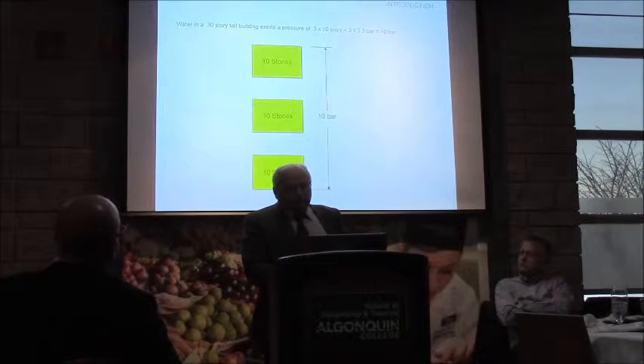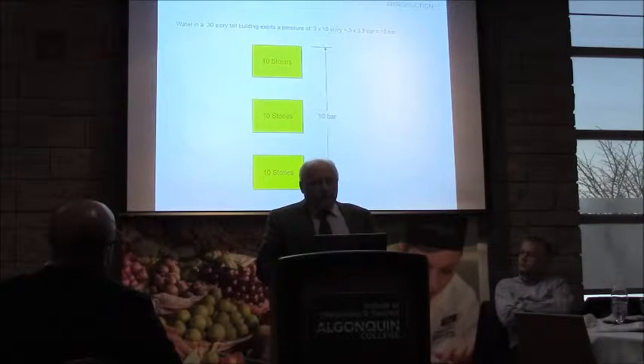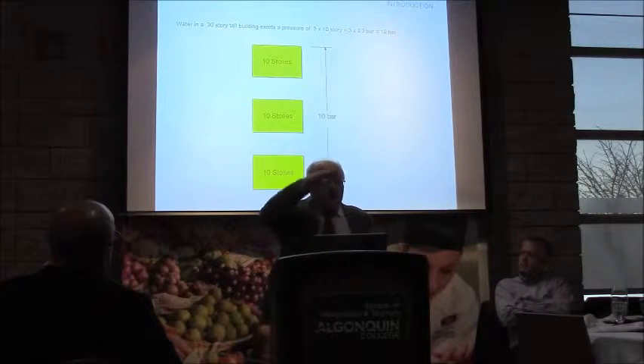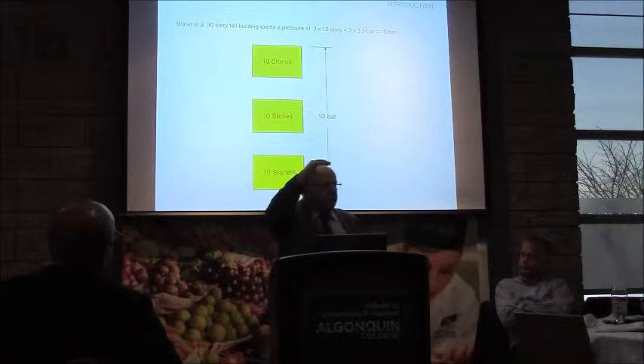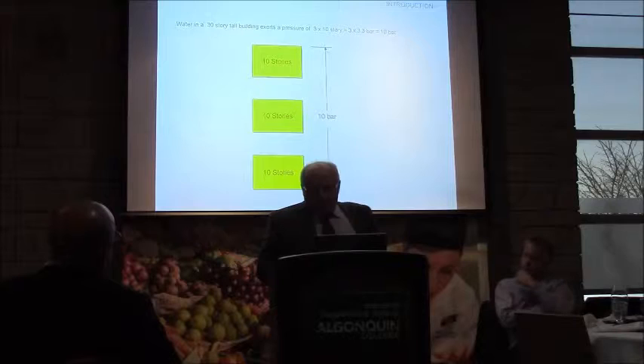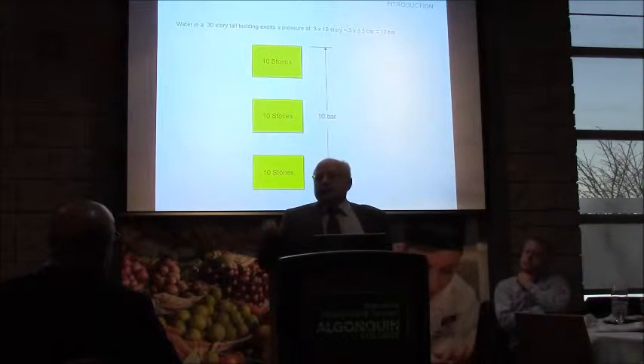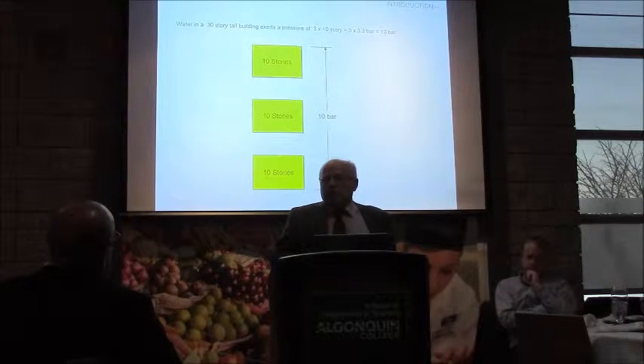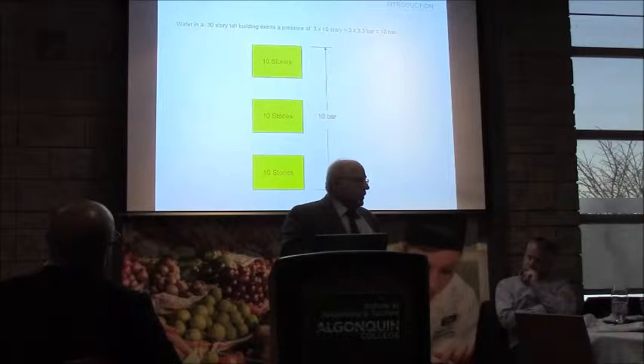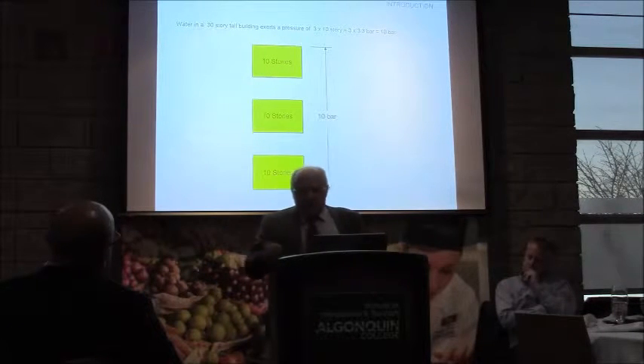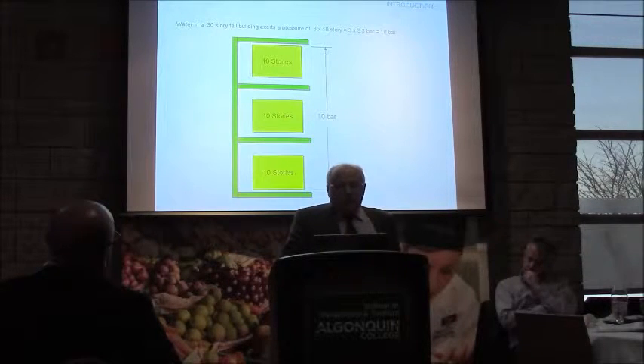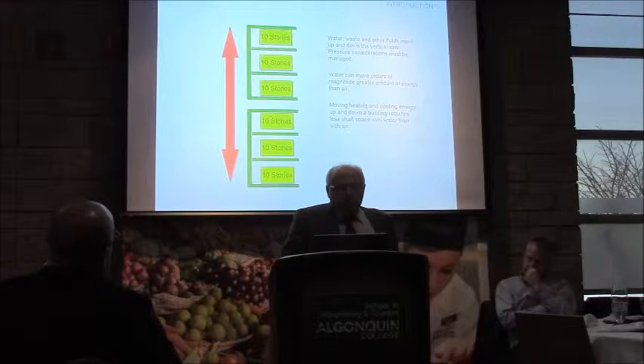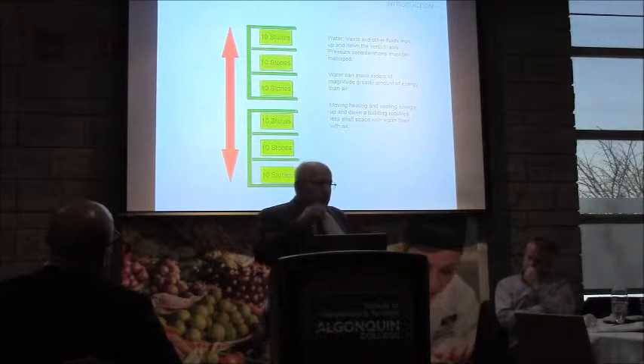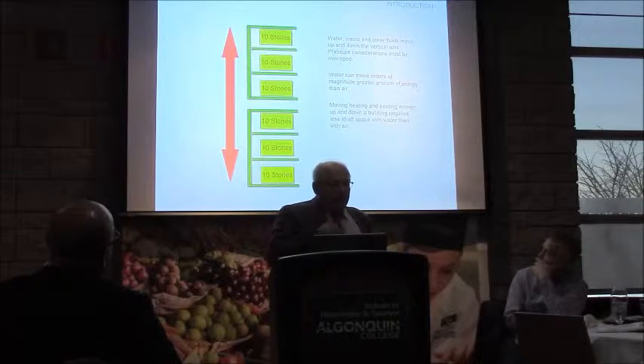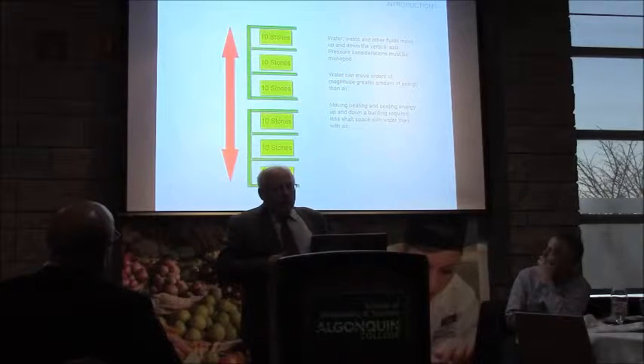Clearly then, the interface pressure with occupants becomes an issue. Material pressure limits and deciding where these breaks occur, is it 10 stories, 12, 9, 8, 15, it can depend on what we're talking about, whether they're systems that have to be closely regulated to a smaller pressure like domestic water, or systems that can have wider pressure variation like closed circuit loops for cooling and heating. But clearly, we can separate a larger building into smaller chunks, and we have an infrastructure that can handle the more rigorous requirements of the overall building.